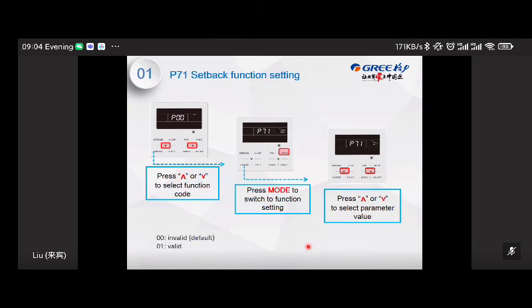Okay. Next one, P71, that's the setback function. For setback, that's a new function. Yeah, that's a new function. This is also for the XK79 keycard controller. So what is the setback function? For the hotel project, it is a little bit special. When the customers go out, they just take out the card, right? And the unit is off, in standby. But when the customer returns to the room, if there has been no running, the room will be a little bit hot in summer, right? So in this case, the experience of the customer may not be very good.